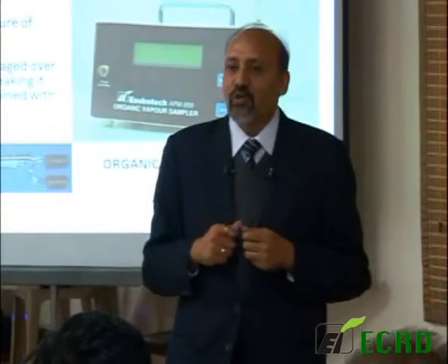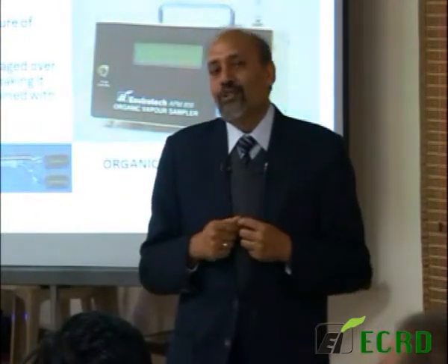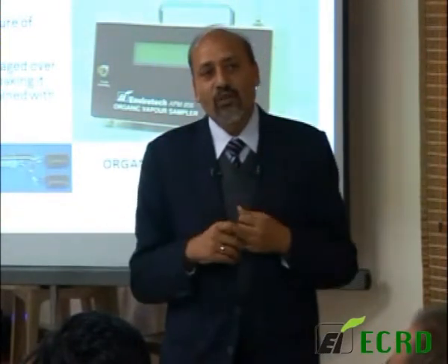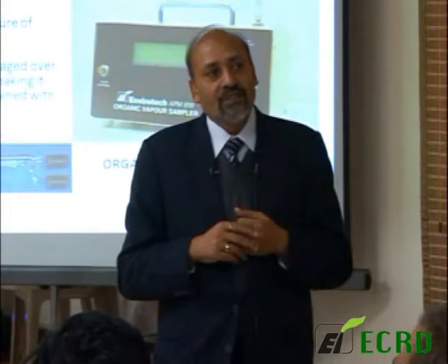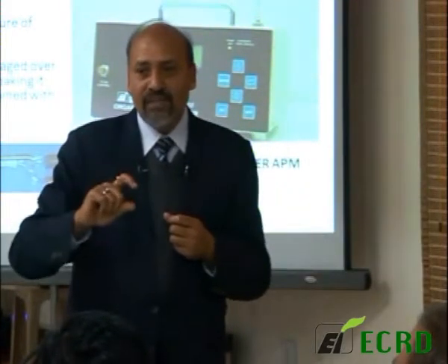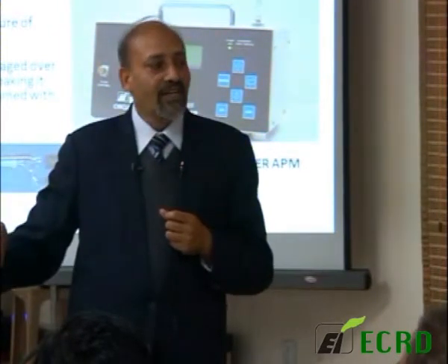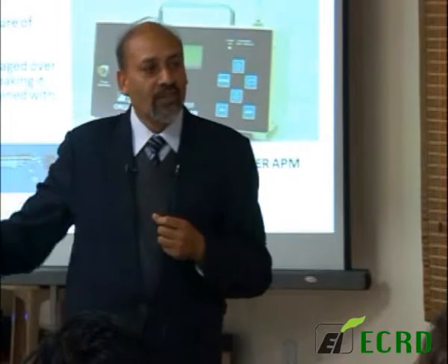saturation of the limited quantity of media available. So compositing says that I need a sample averaged over 8 hours. Why do I need a continuous sample? I will take a sample for a minute, shut down for 5 minutes or 2 minutes, take another sample for 1 minute, and so on.